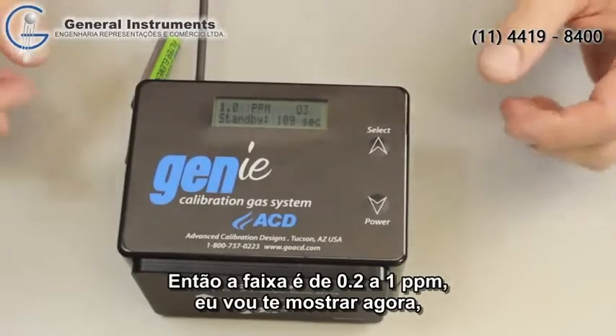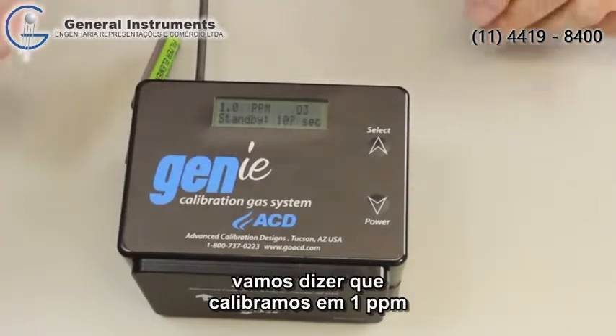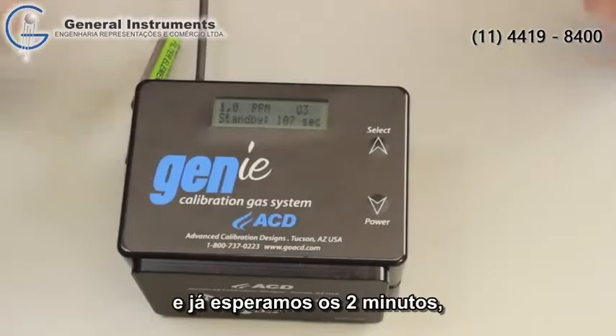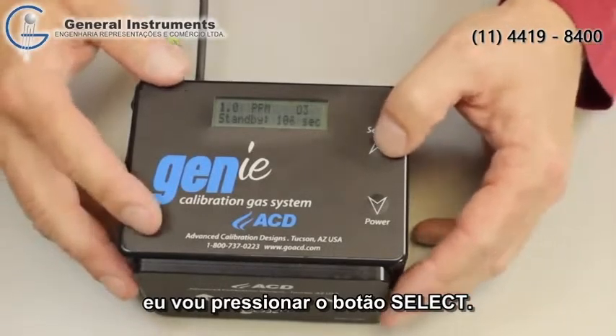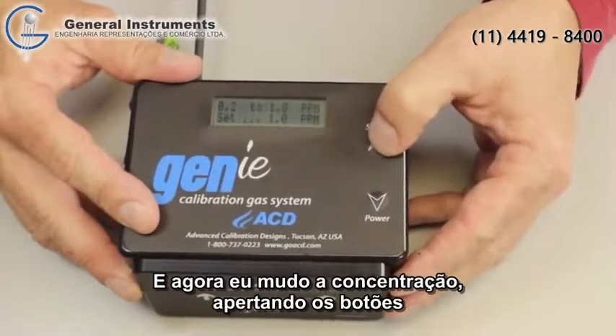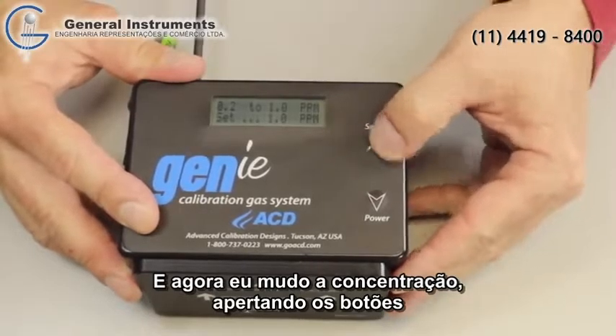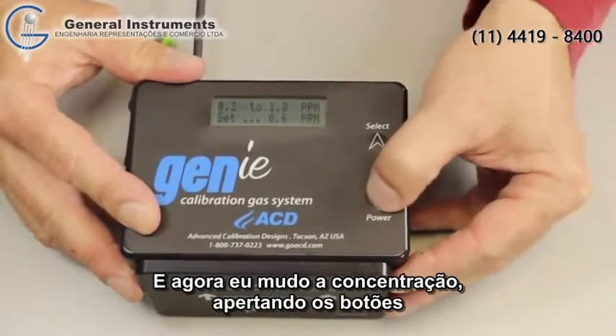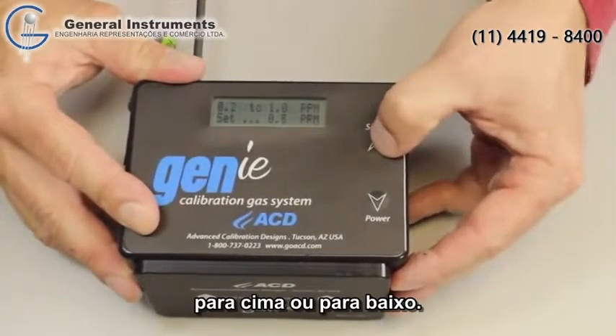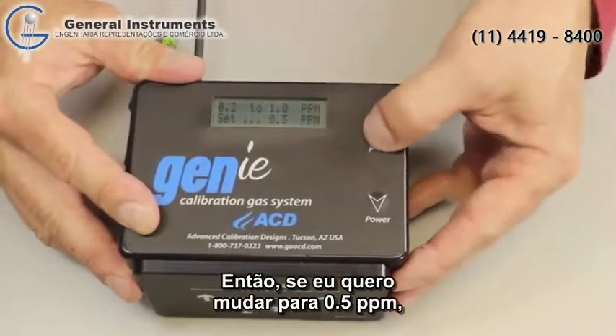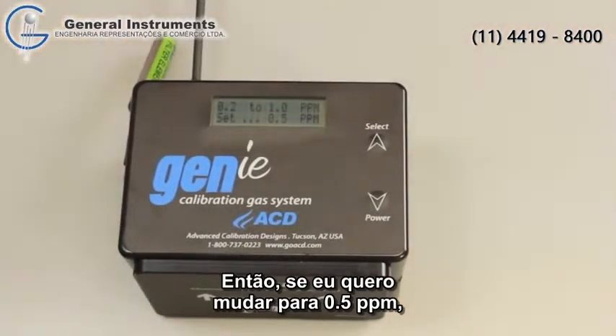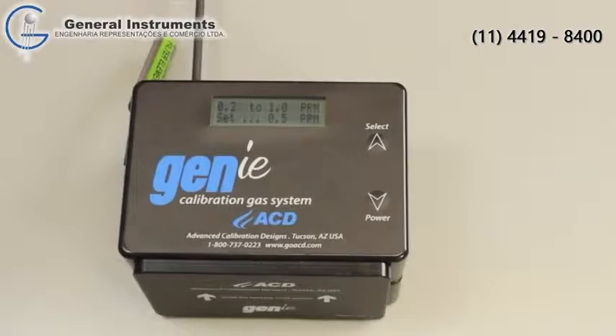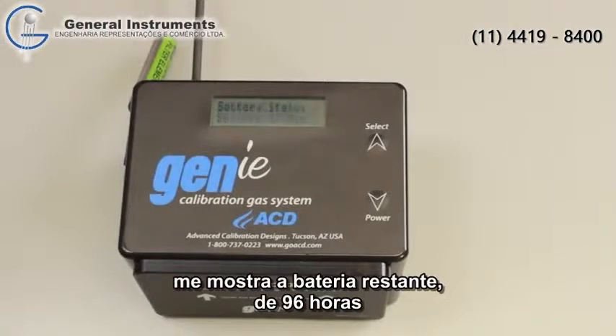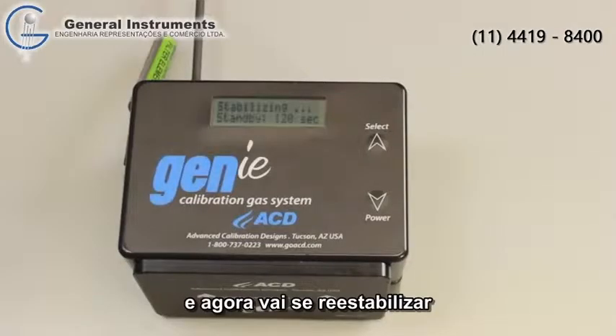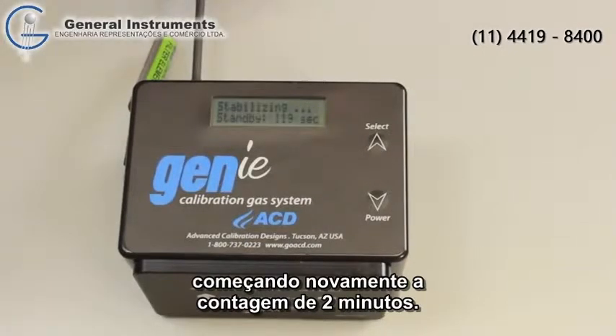So I want to show you now, let's say we've been calibrating at 1 ppm and we've waited the 2 minutes. I'm going to press the select button and then it says select to change. So now these up and down buttons, the select and power, are up and down. So if I want to change it to 0.5 parts per million, it shows me the source life is 96 hours left, battery, and now it's going to restabilize, so it starts over. Okay.